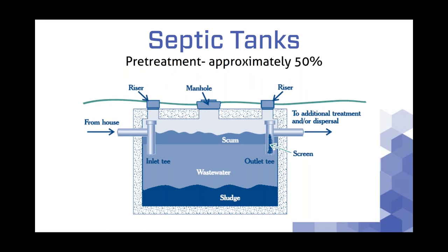Septic tanks are widely used in cluster systems and septic systems in general in the U.S. They're normally made from concrete, plastic, or sometimes fiberglass. There are three distinct layers inside these tanks: the top layer is called the scum layer — floating materials such as tissues and grease from the house. The bottom layer is the sludge layer — solids settling out from the incoming waste. The zone in the middle is called the clear zone, and that's the zone we're trying to pick up effluent from to move it to the advanced treatment system.